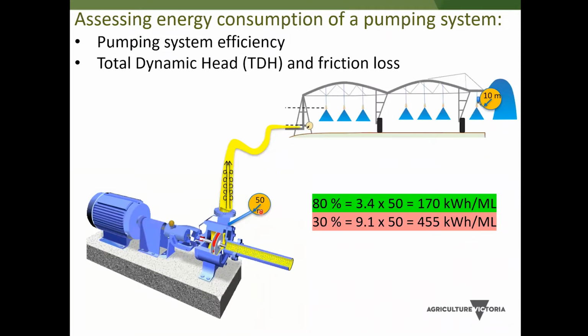The next thing we're going to look at is what pressure that pumping system has to work against to push water through the irrigation system. So as water moves through an irrigation system, there's turbulence and friction loss. And that means that the pressure at the start is higher than the pressure at the end. So in this system, we want to achieve 10 metres of head at the end. We've got to apply 50 metres of head at the pump to overcome all that friction loss. So to work out the energy consumption of the system, we multiply the efficiency factor by the number of metres of head experienced at the pump.